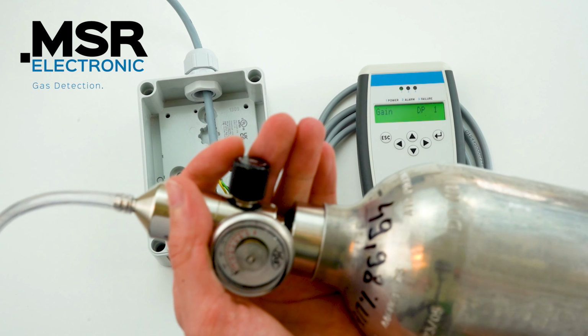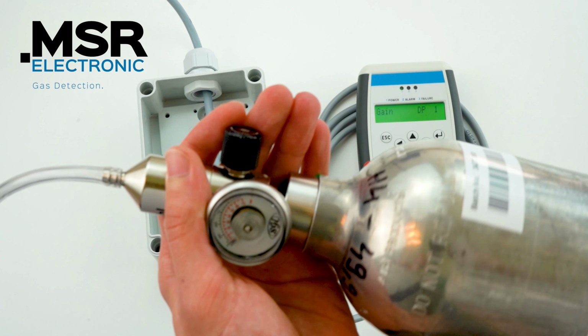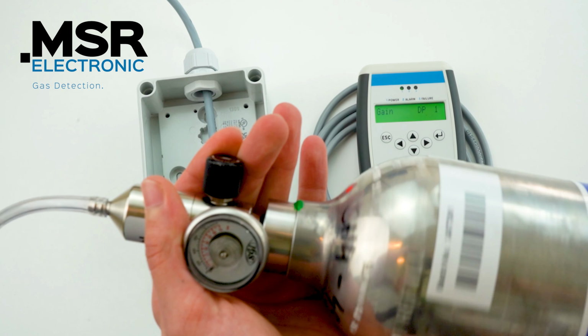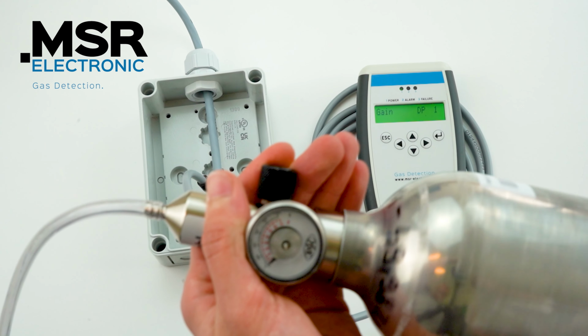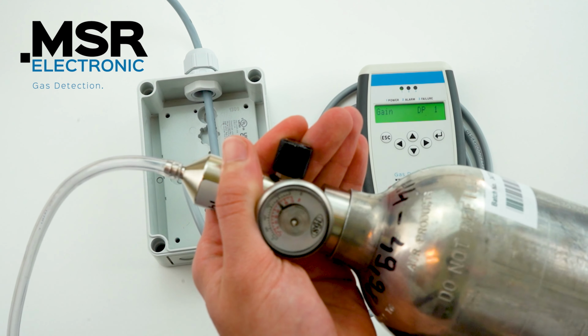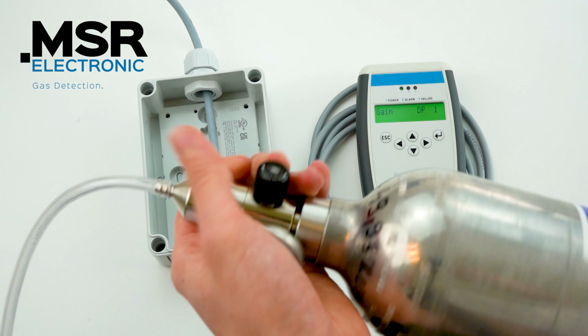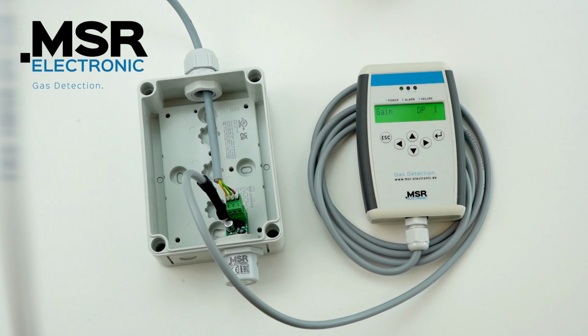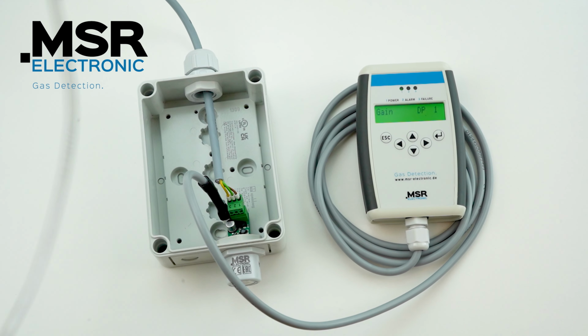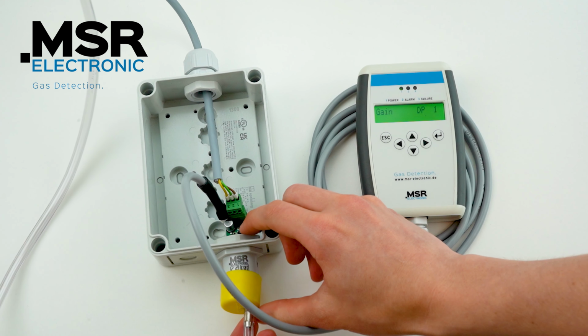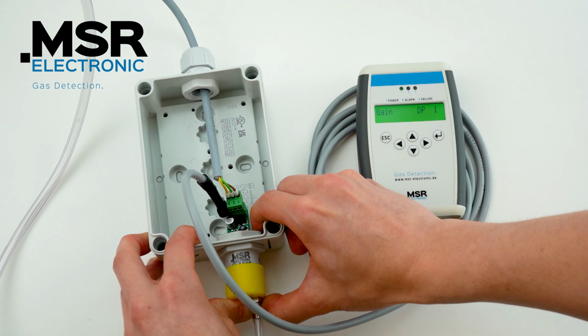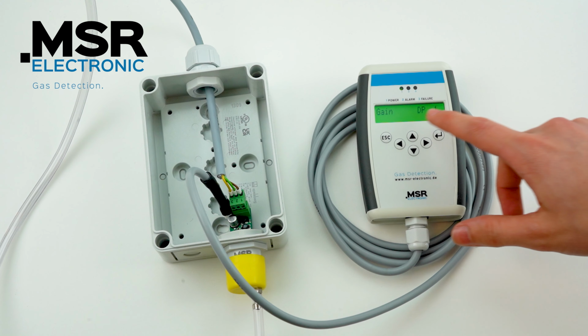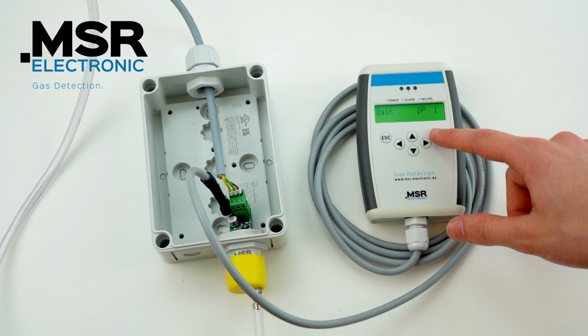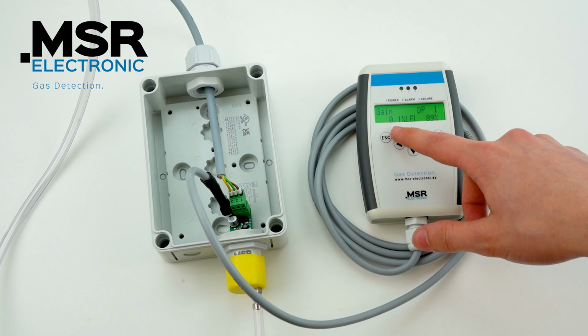The process is almost identical to the zero calibration. As soon as you press the enter button, the current gas value and the sensitivity value of the sensor are displayed. If the sensitivity of the sensor is below 30%, calibration is no longer possible. Now the calibration can be started by pressing the enter button and the flow regulator is opened. The calibration mode is indicated by the underline as before.